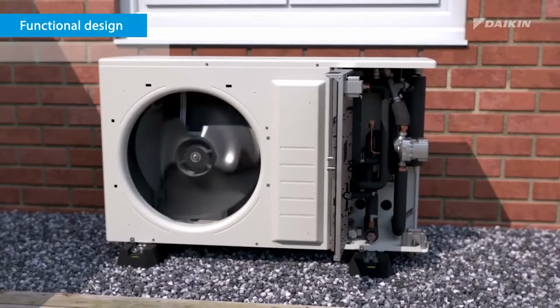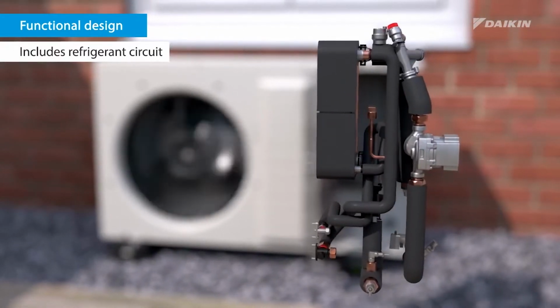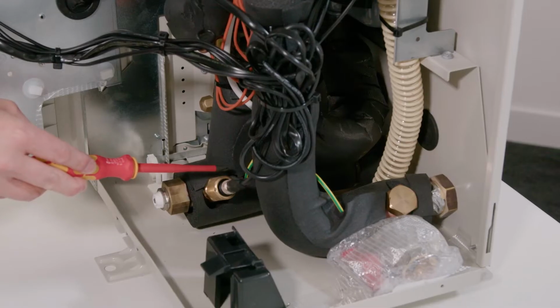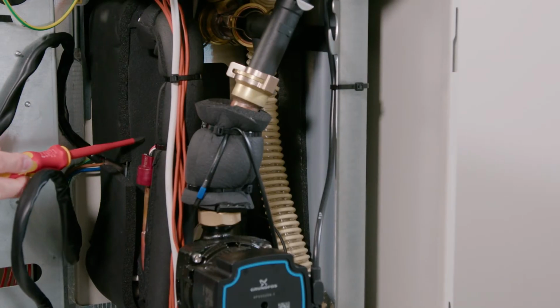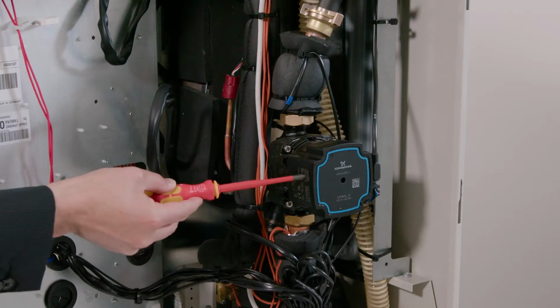This system is a true monobloc, which means that all its hydraulic components are supplied integrated with the outdoor unit. The outdoor casing contains components such as flow sensor, water filter, stop valve, plate heat exchanger, expansion vessel and circulation pump. One of the major reasons for the system's high efficiencies is because it uses R32 refrigerant, which has a low global warming potential and a much better performance compared with any R410A based heat pump system.